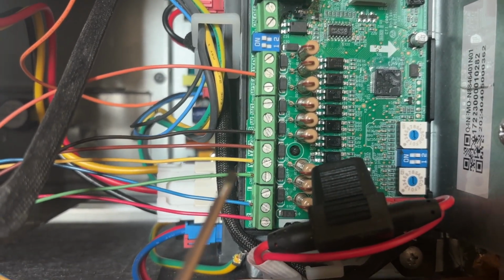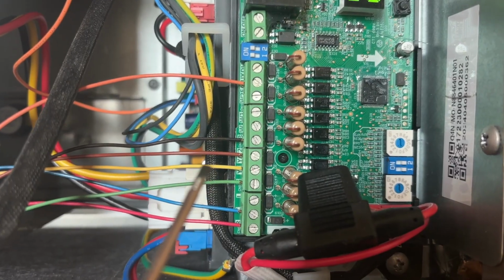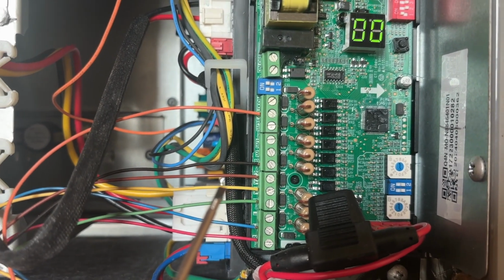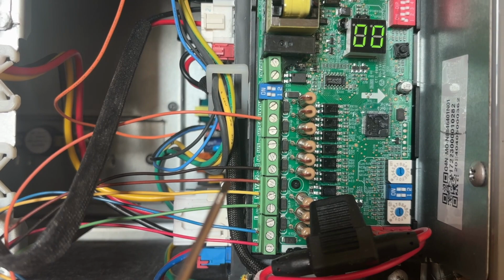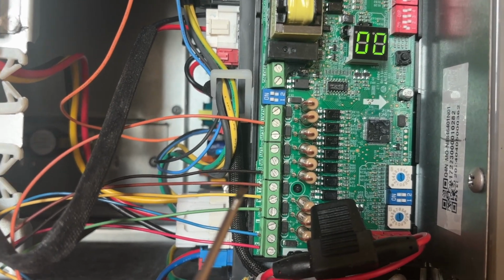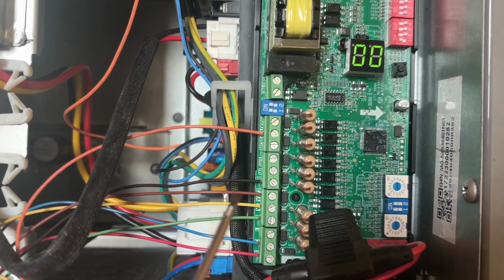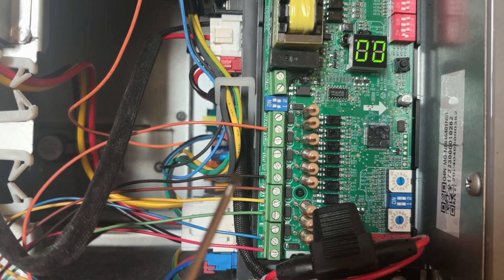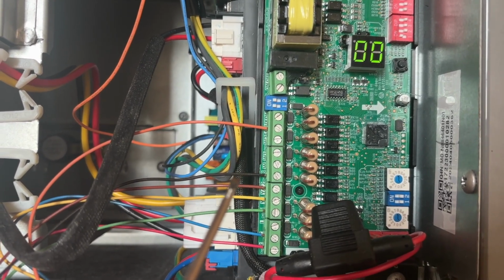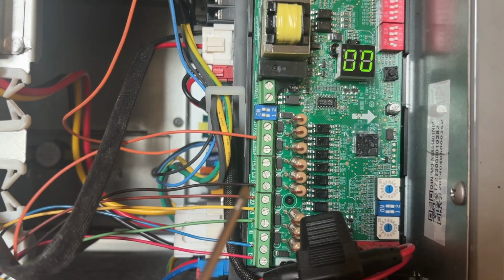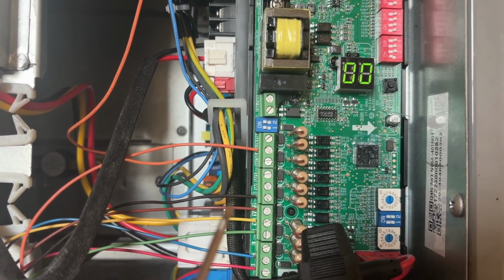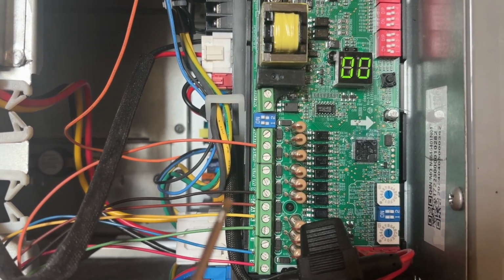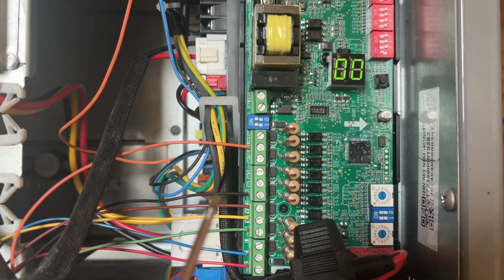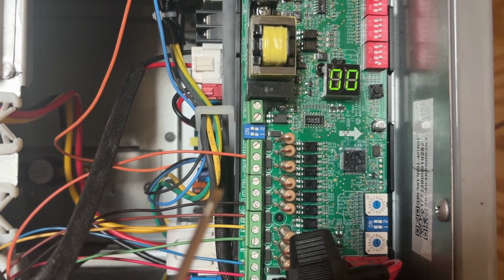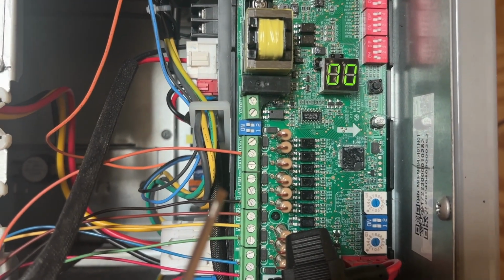Green is for the fan control. Yellow is Y1 for your first stage heating or cooling, depending on where the reversing valve is. Brown is stage 2 heating and cooling, again depending on where the reversing valve is. Black is the reversing valve control itself. The VersaPros are set up to be a B control. So when you set your Nest thermostat up, make sure you select B for the reversing valve in the configuration, because it's going to have one hookup, O and B.